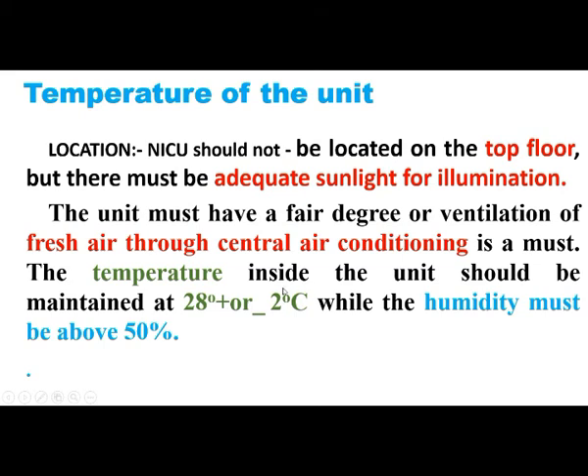The location should never be at the top floor; the walls, if open, or the light source must come from outside. So any two of the walls must be on the outside area. This is the location of the NICU, and the temperature must be maintained at 28 degrees plus or minus 2 degrees Celsius, with humidity of 50% or above. That covers location and temperature.